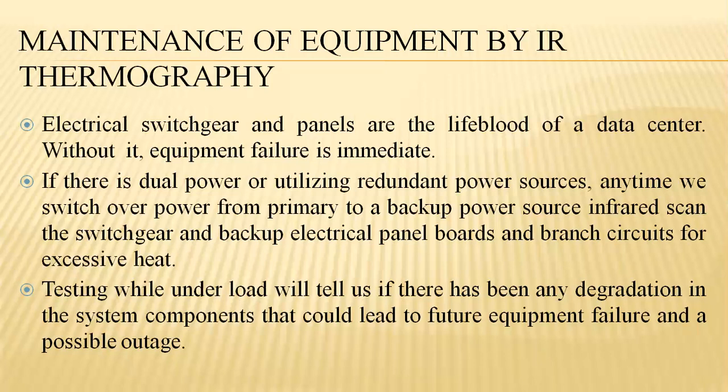Normally, if there is dual power utilizing redundant power sources, anytime we have a switch over from the primary to a backup power source, an infrared scan of the switch gear and the backup electrical panel boards and circuits is done to look for excessive heat, and for components that could lead to future equipment failure in the case of degradation within the system, caused by degradation under heavy load that has been progressing over time.